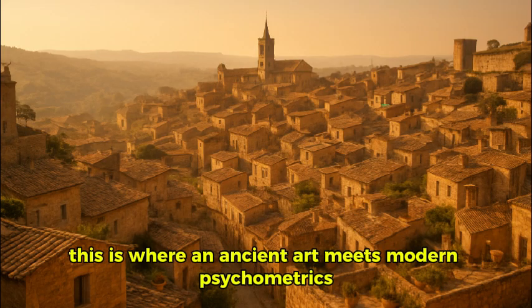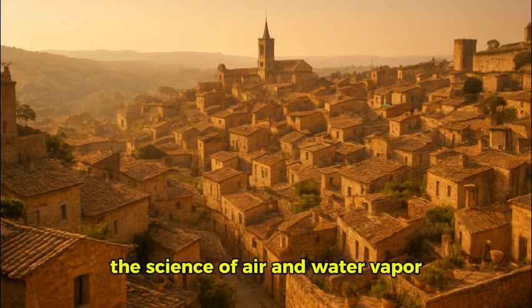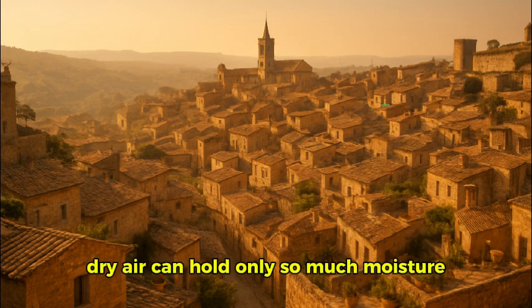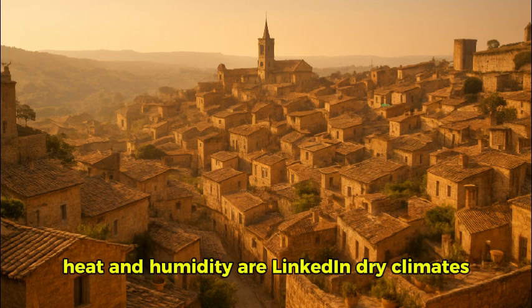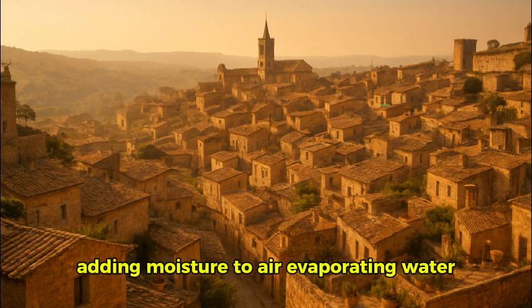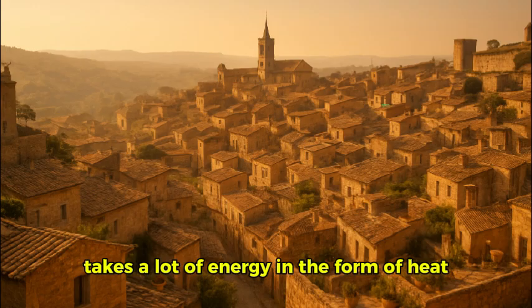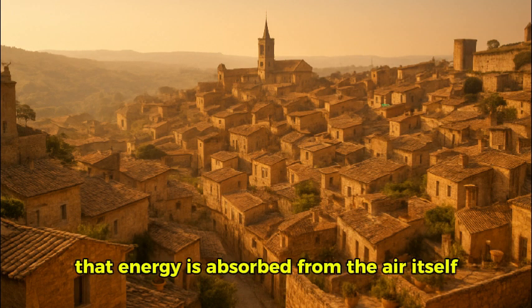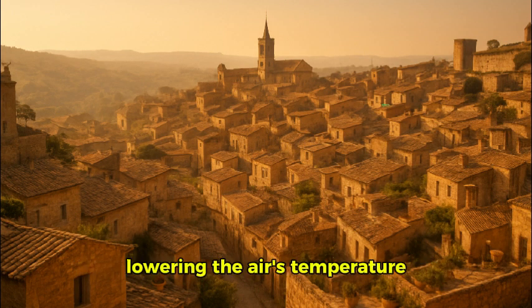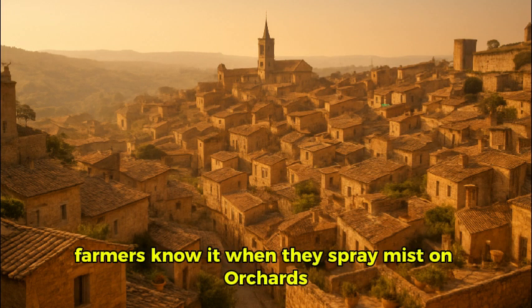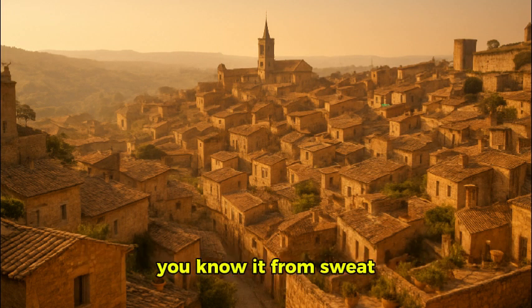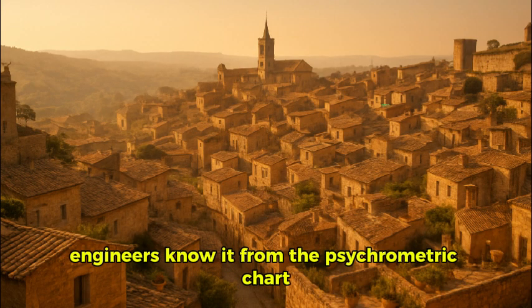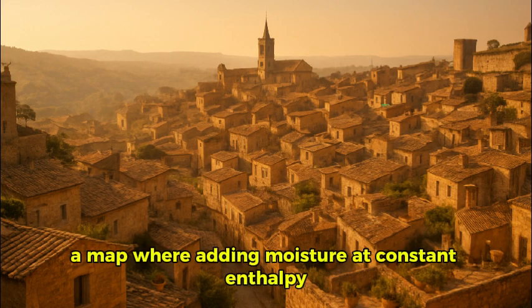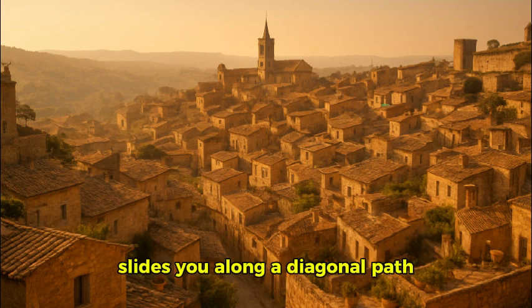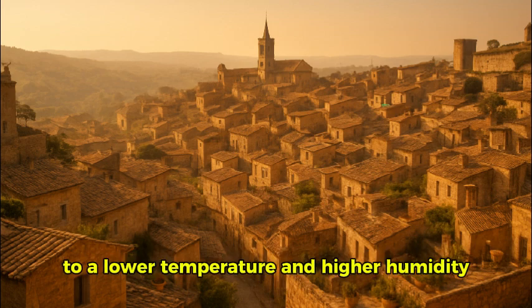This is where an ancient art meets modern psychrometrics, the science of air and water vapor. Dry air can hold only so much moisture. Heat and humidity are linked. In dry climates, adding moisture to air, evaporating water, takes a lot of energy in the form of heat. That energy is absorbed from the air itself, lowering the air's temperature. This is evaporative cooling. Farmers know it when they spray mist on orchards. You know it from sweat. Engineers know it from the psychrometric chart, a map where adding moisture at constant enthalpy slides you along a diagonal path to a lower temperature and higher humidity.